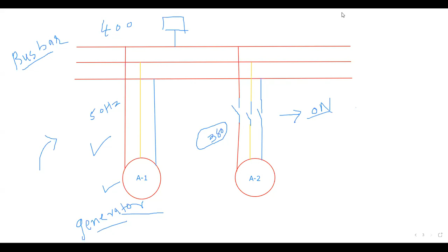Okay, I'm repeating. Please focus right now. This is alternator 1 or generator 1, which is connected to the bus bar. You know about the bus bar? This is the bus bar to which the load is connected. Now this alternator is already connected to the system and it is generating 400 volt at frequency 50 Hz. And this alternator 2 is right now generating 380 volt. Now, if I connect this alternator 2 to the bus bar, then what will happen? What will happen if I connect alternator 2 with the bus bar?